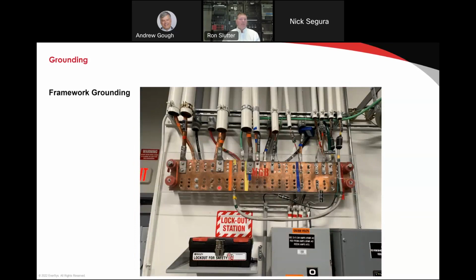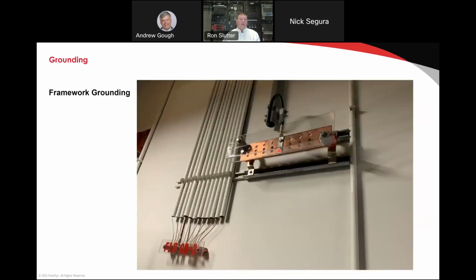Okay, this is a bar that has 2 sets of holes, right? But look where all the connections are, all on one side. They're all next to each other. So producers have to come in and absorbers have to go out without being next to each other. Very, very important. A typical continuity test is not going to show this. You put 100,000 amps of current flow on this ground bar and it will not work. Same thing with this one. We got a big choke here going into the conduit. This actually turned into an RF antenna and injected all the RF signal into the ground system and was disrupting load all over the place. Here you can see very obviously we have an absorber, this larger conductor, and all of these producers, but they're right next to each other. Again, it will not work.